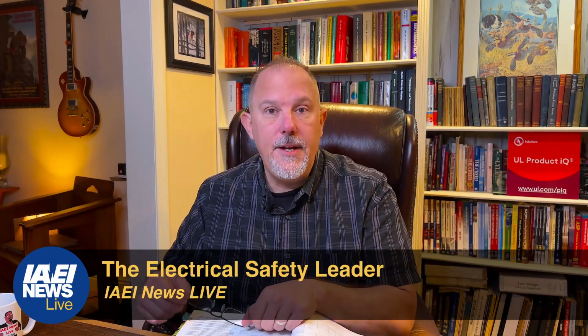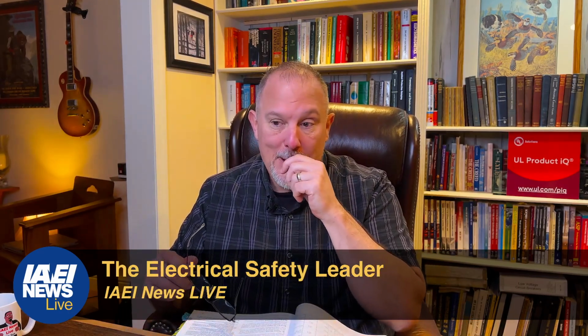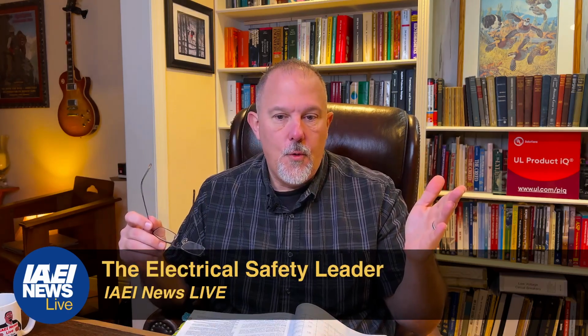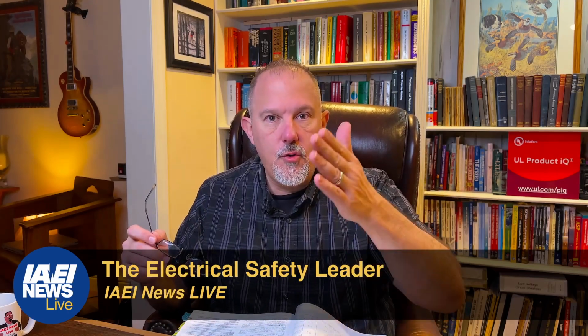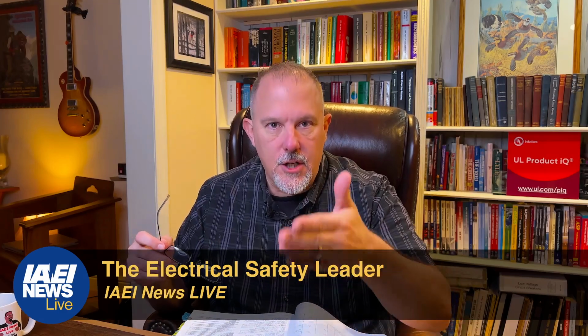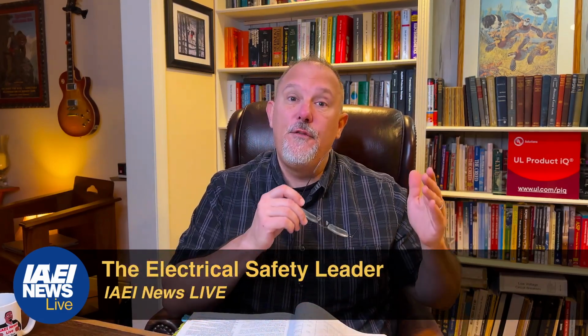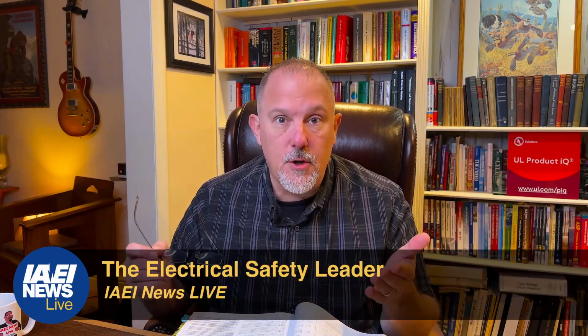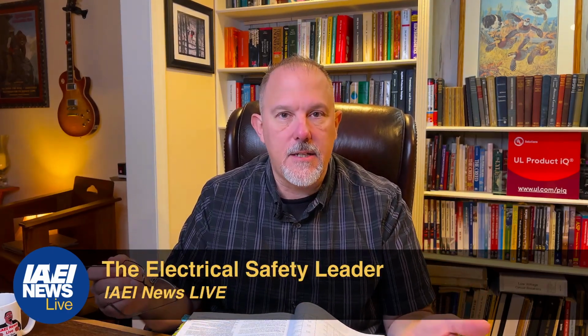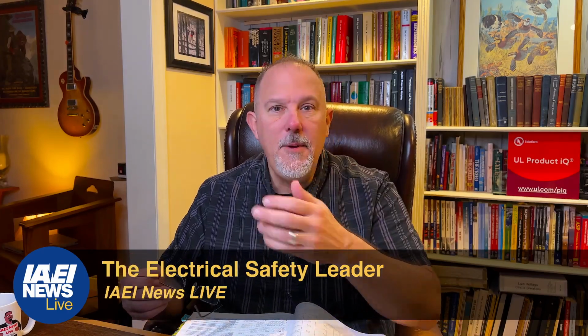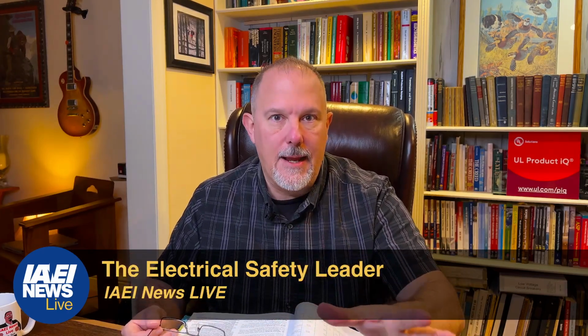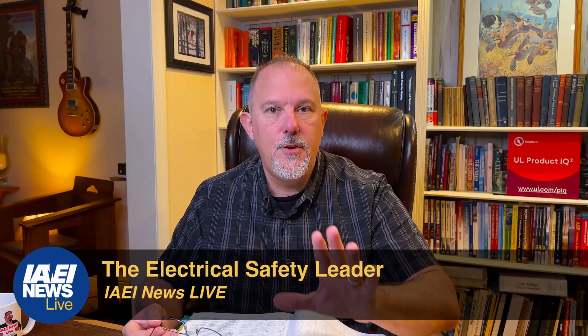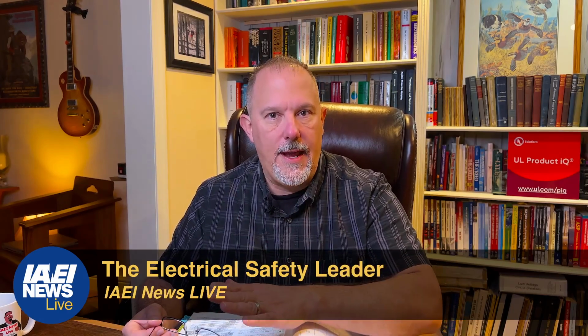So you had an AHJ who would say, look, you cannot use the equipment grounding conductor as a current return path because that is a violation of Article 250 requirements for objectionable currents. You're powering the device. You can't do that. I mean, we're talking milliamps, right? But still, you're not permitted to do that.